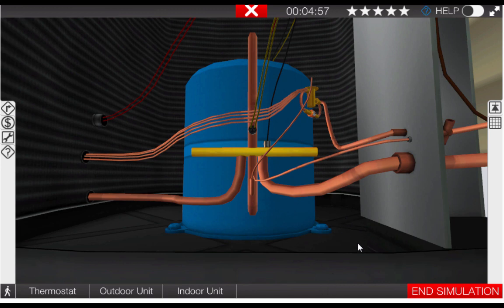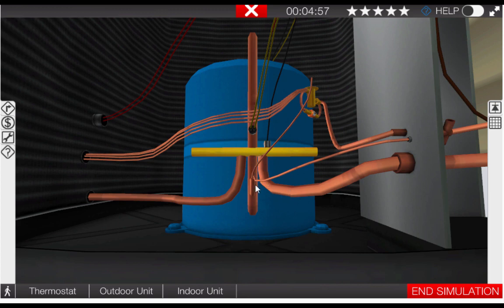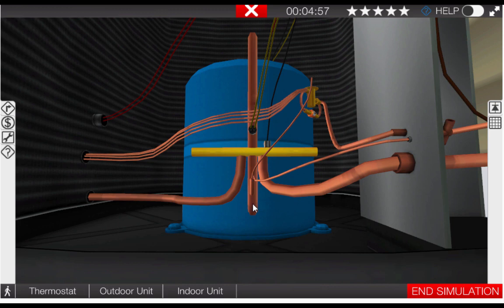So we may see something like this on this port here coming into the valve we may measure 53 degrees Fahrenheit. When the suction vapors leave the valve through the permanent suction port back to the compressor maybe we're measuring 63 or even higher. This indicates at least a 10 degree pickup in temperature as the suction vapors pass through the valve. This is the result of discharge gas coming into the top port leaking through the valve body and into the suction port.